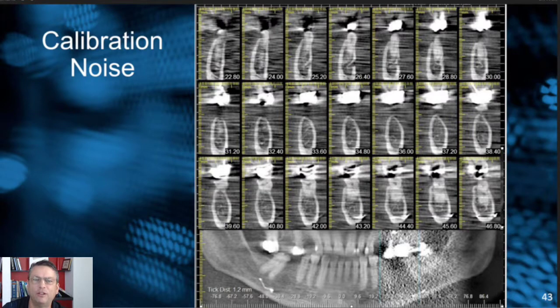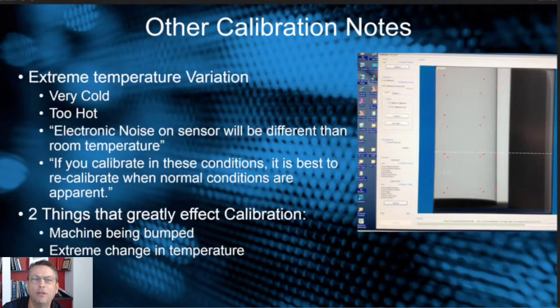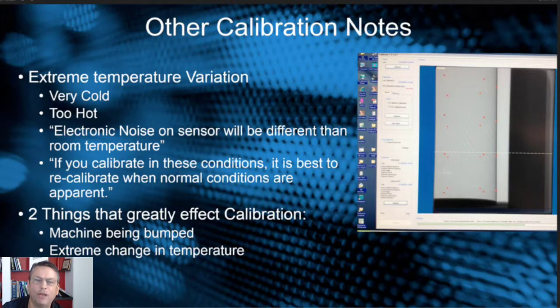Other calibration notes: extreme temperature variation could affect your image quality — very hot or very cold. If you have an office in a hot part of the country where it starts out cool in the morning but a window lets the sun bake onto the sensor, that extreme temperature variation can affect your image quality. Electronic noise on the sensor will differ from room temperature. According to the engineers, if you calibrate in extreme hot or cold conditions, it's best to recalibrate when normal conditions return. If your machine is next to a window with extreme temperature variations, it doesn't hurt to calibrate once in the morning and once after lunch.